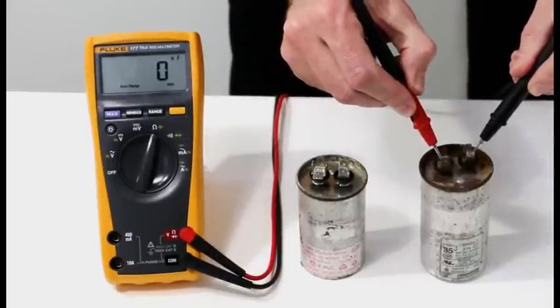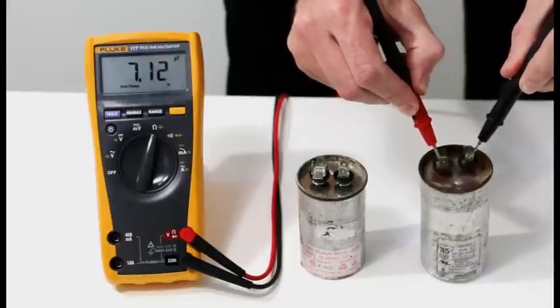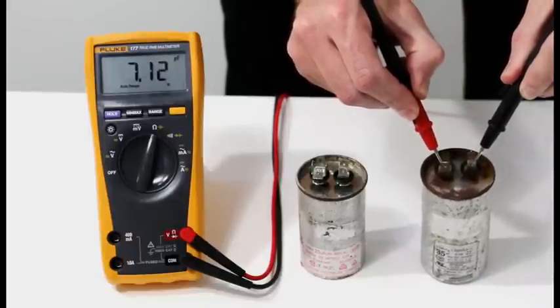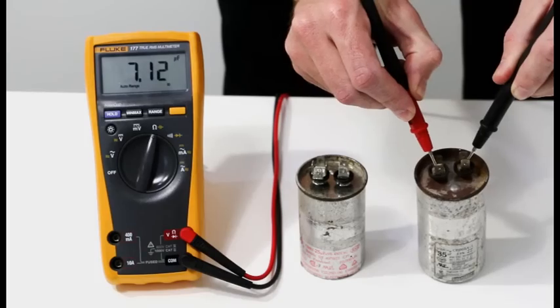This unit over here is my 35 microfarad capacitor. It's only measuring 7 microfarads. This unit has failed.